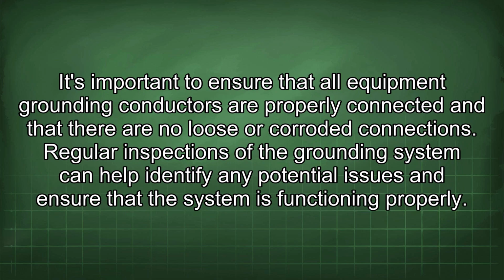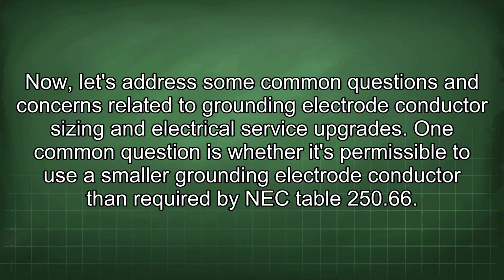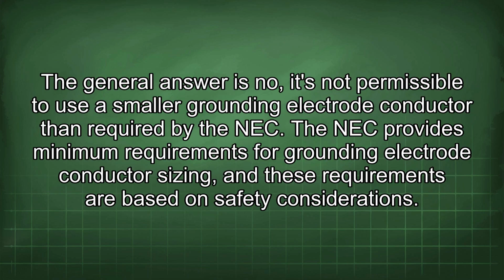It's important to ensure that all equipment grounding conductors are properly connected and that there are no loose or corroded connections. Regular inspections of the grounding system can help identify any potential issues and ensure that the system is functioning properly. Now, let's address some common questions and concerns related to grounding electrode conductor sizing and electrical service upgrades. One common question is whether it's permissible to use a smaller grounding electrode conductor than required by NEC Table 250.66. The general answer is no.